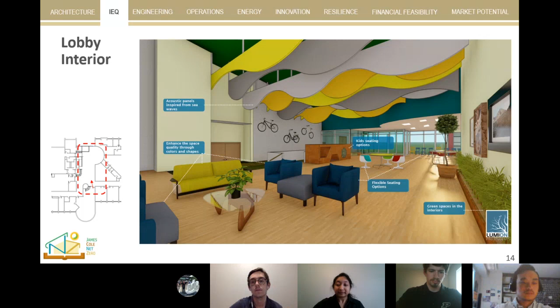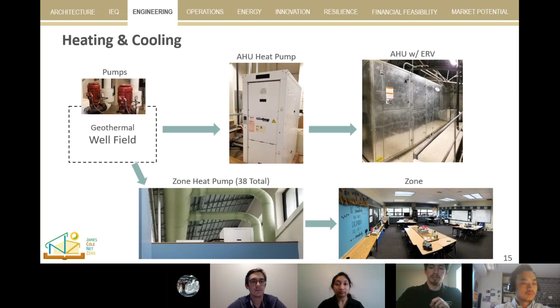Thank you, Bhavya. Engineered with energy efficiency in mind, the single-story, double-stacked corridors are ideal for heating and cooling, with all rooms having external wall or roof exposure, reducing thermal reservoirs. A geothermal well loop is used for heating and cooling throughout the school, as well as individual zone heat pumps. The heat pumps are connected to the well loop as shown for zone heating and cooling based on demand and well field temperatures. The intelligent engineering design of zone heat pumps allows for individual zone conditioning, heating northern classrooms while cooling southern classrooms on a sunny day in spring, providing comfortable and efficient indoor environmental quality.